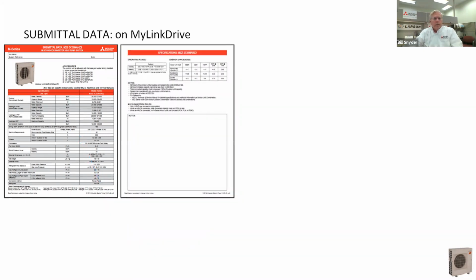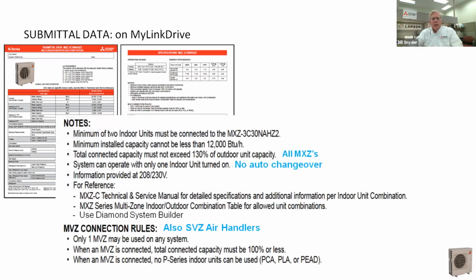Page 2, and this is an MXZ. There are some notes up here giving you the efficiency of the various indoor heads that are on the unit. Then there's a notes page down here that you might reference. This happens to be for a 3C30. It's telling you the minimum installed capacity is 12,000 BTU. So on this 30,000 unit, you could put enough heads to give you just 12,000, like putting 2 6s on here. That's fine.